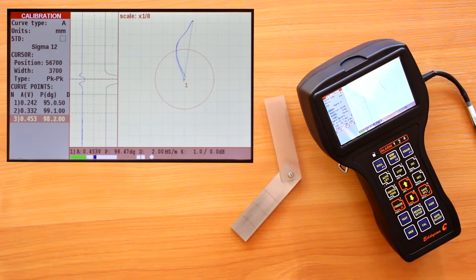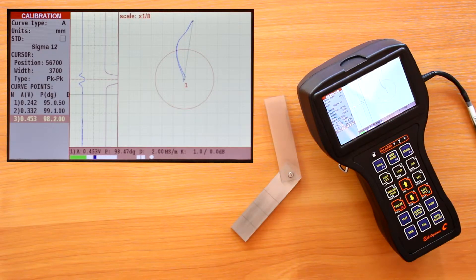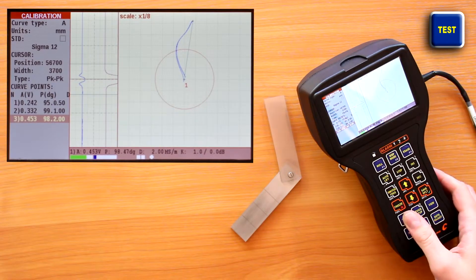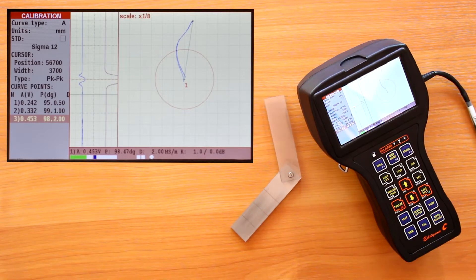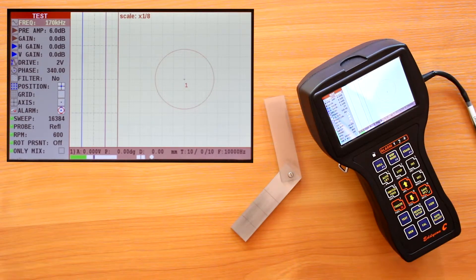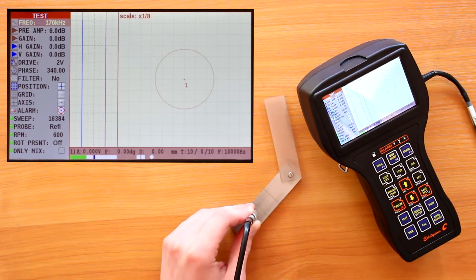To make sure that the curve is plotted correctly, it is necessary to perform a checkup on the same standard as follows. In the test menu, place the ECP on the flaw-free section of the reference standard before any flaw and press F1 key for balancing.